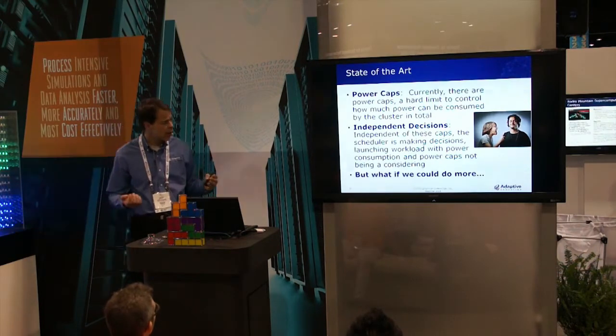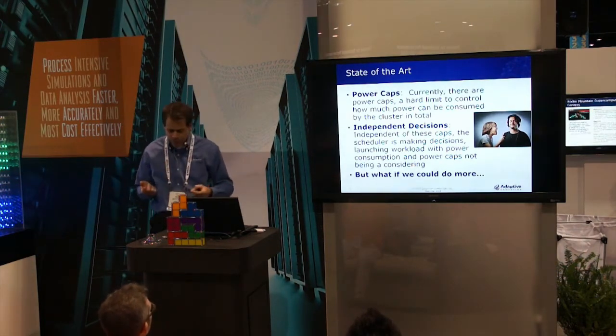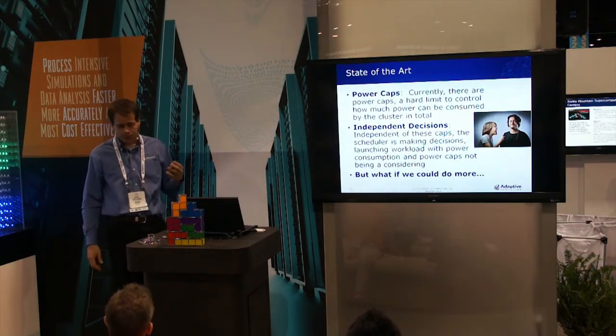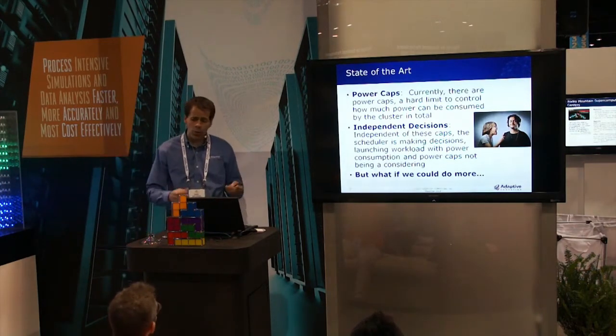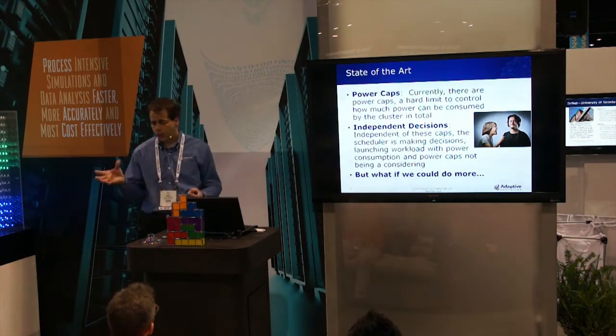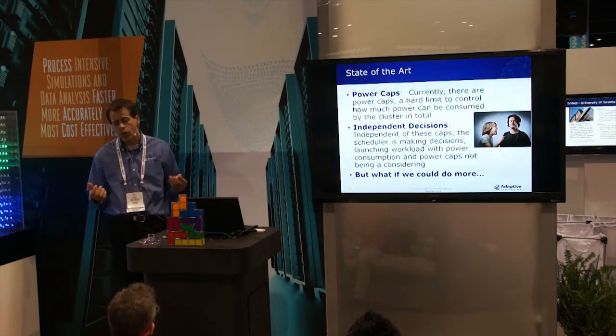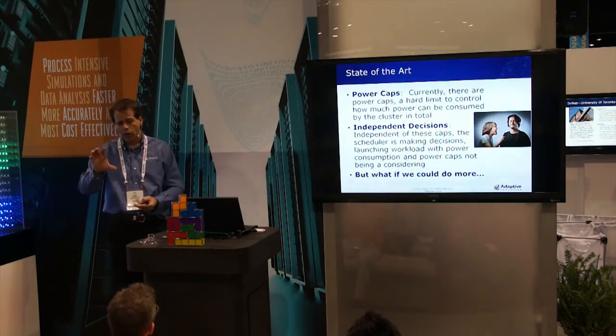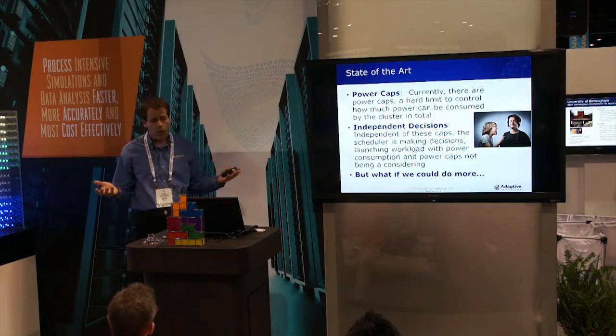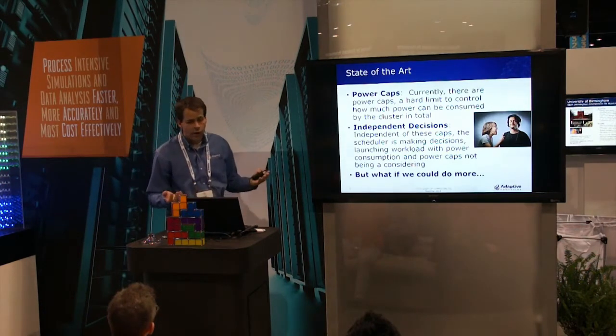Well, to respond to that, some of the hardware vendors have enabled the capability where you can control the power that flows through a PDU. It may be rated for a certain thing, but via a software control, you can go in and say, I'm throttling you. I'm going to limit the amount of power that flows through. If you have these hard power caps, then it's a piece of cake to go ahead and enforce it.